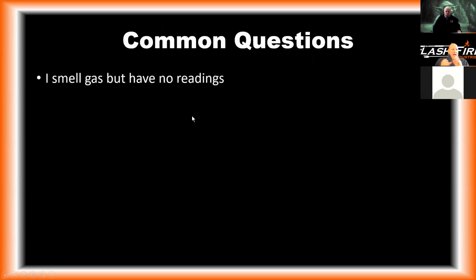So common questions. I smell gas, but I have no readings. We touched on this a little bit. If we're not using a leak detector, there's a very good chance that we have a very low level of gas that is not registering on our LEL sensor. On the flip side, I don't smell gas, but I do have readings, whether it be on our LEL sensor or on our leak detector.